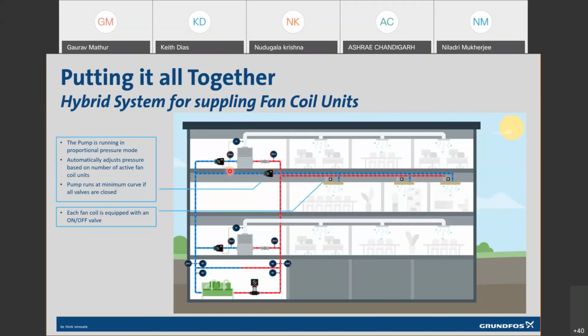So in a hybrid system, you have AHUs being controlled based on temperature, and FCUs controlled proportionally based on the pressure sensor, or differential pressure sensor. Now, as I have mentioned, this differential pressure sensor is already inbuilt in the pump, so you need not put any separate sensor. The moment you put the pump and set it across the FCUs, you put the set point as the friction loss in that particular circuit, and you are ready to go. So this is how the whole system becomes much simpler, and there is localized control which makes the commissioning very, very easy.